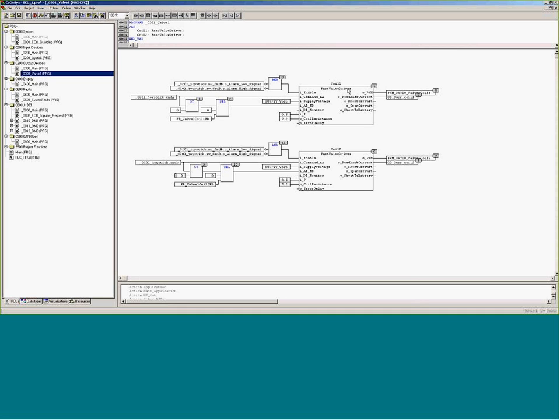We're driving a fast valve driver. Information on these can be found in the resources tab under these libraries. But the enable command says I want to make sure that I'm not in a low alarm status or a high alarm status. If I'm not, that little invert circle there tells us that it's a not signal. Comes into the and block, both this and this is true. Then it's going to enable the fast valve driver block.